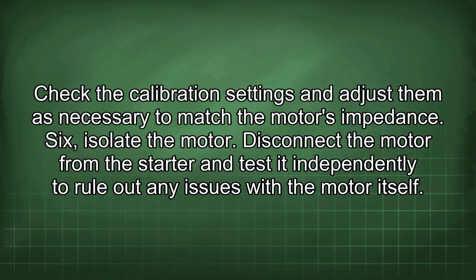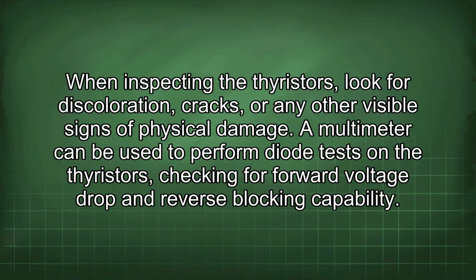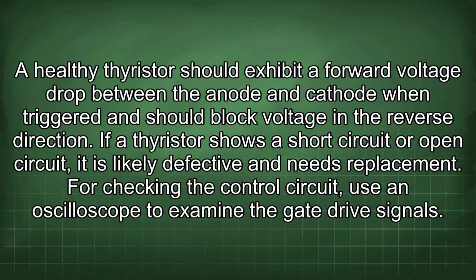When inspecting the thyristors, look for discoloration, cracks, or any other visible signs of physical damage. A multimeter can be used to perform diode tests on the thyristors, checking for forward voltage drop and reverse blocking capability. A healthy thyristor should exhibit a forward voltage drop between the anode and cathode when triggered and should block voltage in the reverse direction. If a thyristor shows a short circuit or open circuit, it is likely defective and needs replacement.